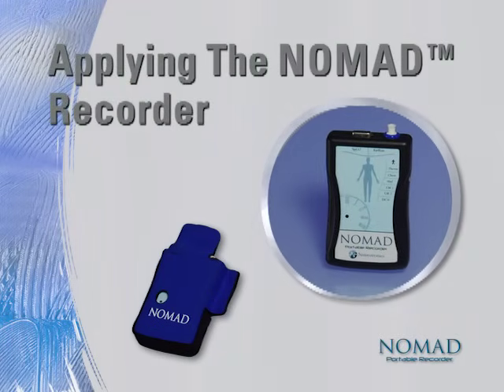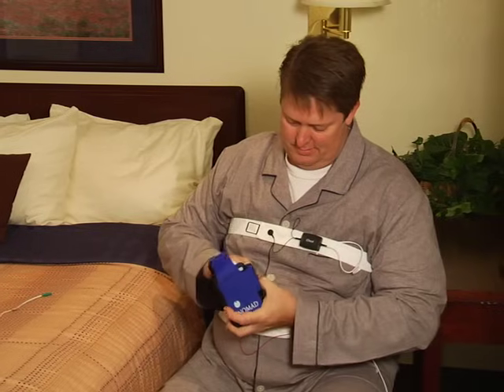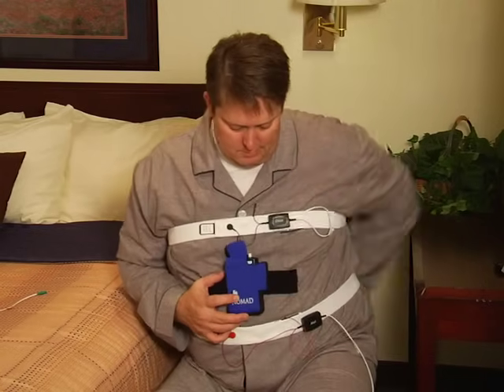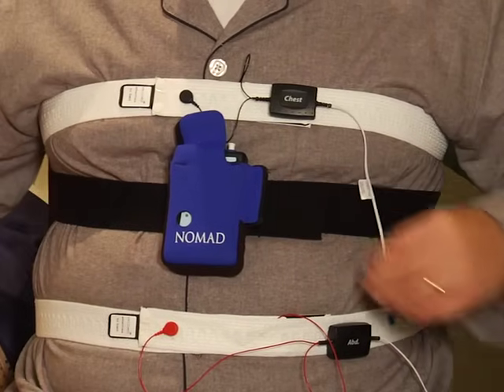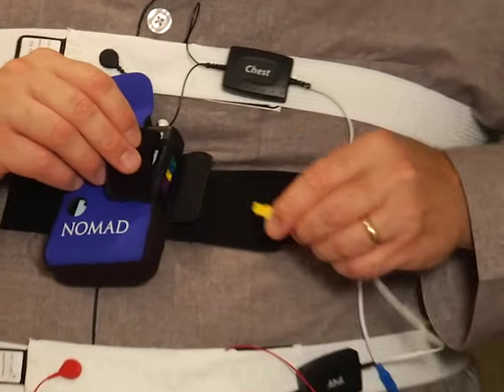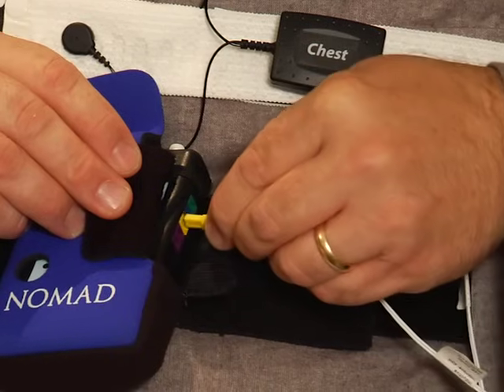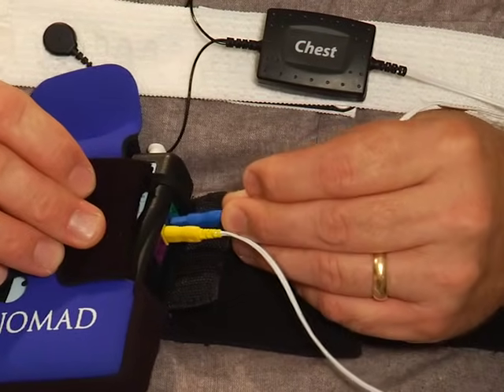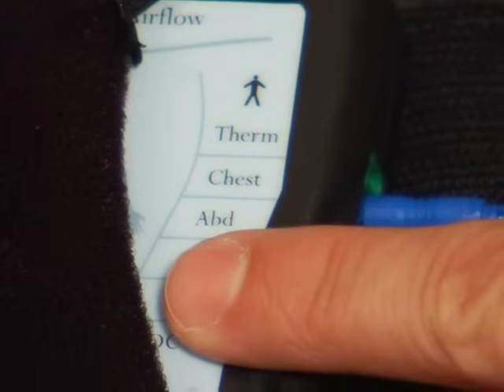Applying the Nomad recorder. Now it's time to put on the Nomad recorder and pouch. As you hold it up to you, the word Nomad should be facing away from your chest. Wrap the belt around your body, positioning the Nomad at the center of your chest, just below the chest belt. Affix the Velcro tab and make sure it fits snugly against you. Next, plug the yellow connector into its matching colored input on the Nomad recorder. The connectors are keyed, so they can be inserted in only one direction. You can now plug in the blue chest connector in exactly the same fashion. In addition to being color-coded, the ports are also labeled ABD and CHEST.